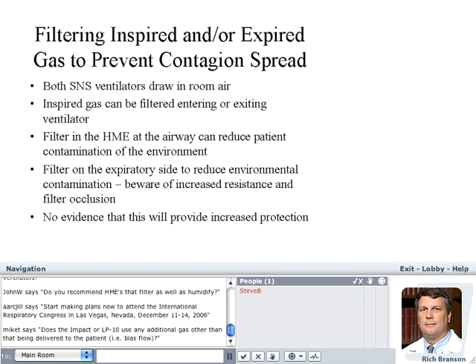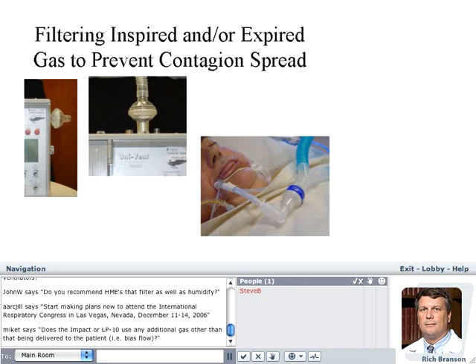You might put a filter on the expiratory side, and some of the guys from Canada who were in the SARS epidemic told me they were glad to have, I think they were using mostly 7200s that had the heated expiratory filters, and they felt that that improved their safety. Although I believe them, my reading of the literature doesn't suggest that that's ever been proven. This just shows you the Impact 754 on the far left. You see that's the filter going into the inlet of the machine, and in Iraq this is important because it keeps the sand out of the ventilator and out of the patient from the environment.